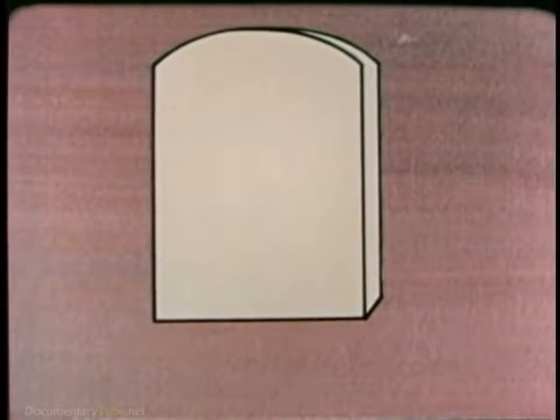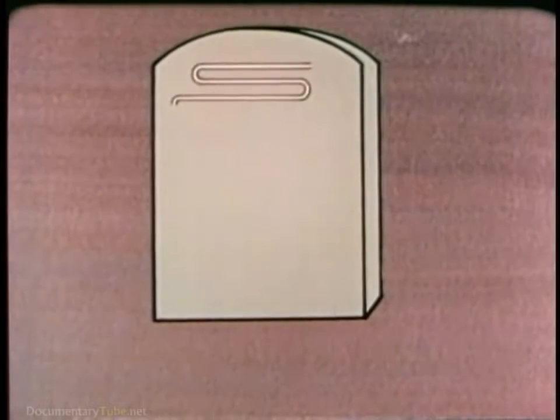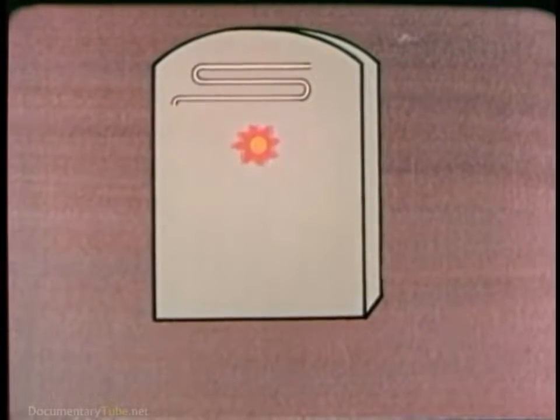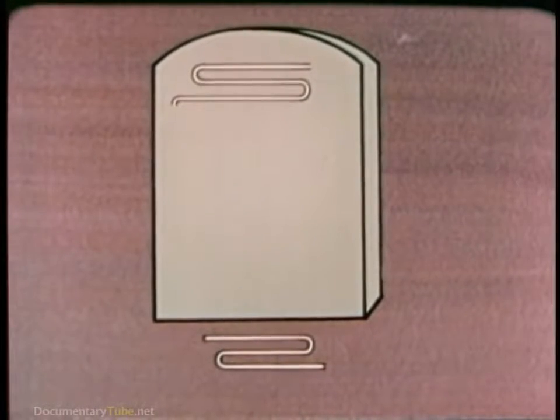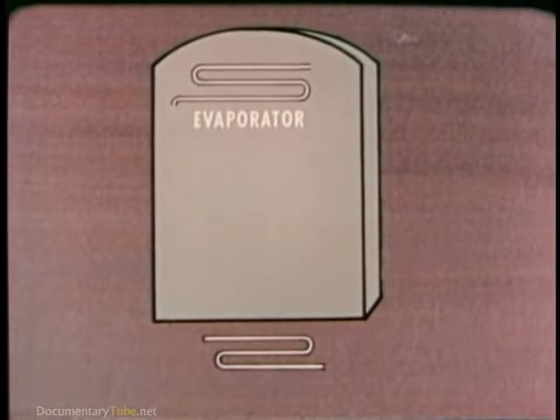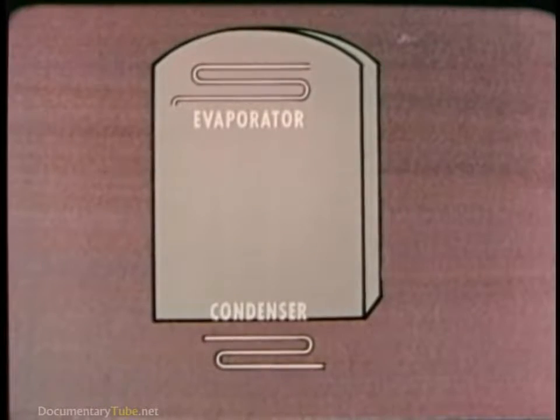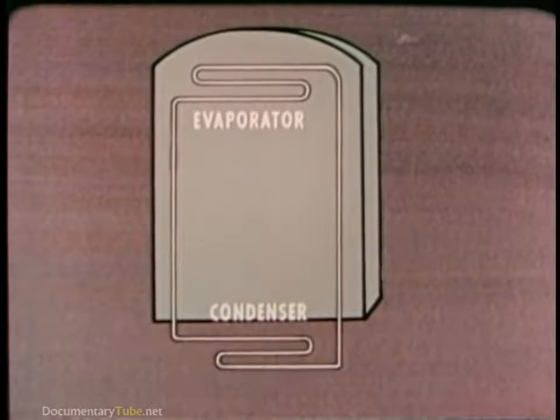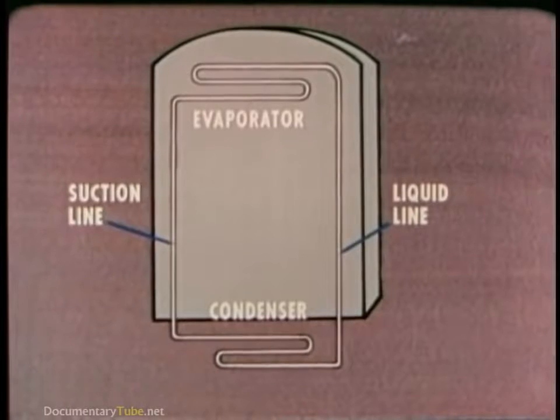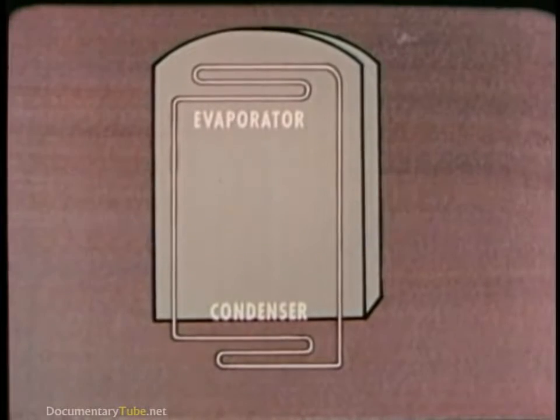Refrigeration is the transfer of heat from a place where it is not wanted to a place where it is unobjectionable. To do this, a refrigerator uses a unit inside the box that takes up heat and a unit outside the box that gets rid of it. These units are called the evaporator and the condenser. They are tied together by connecting lines, referred to as the suction line and the liquid line.